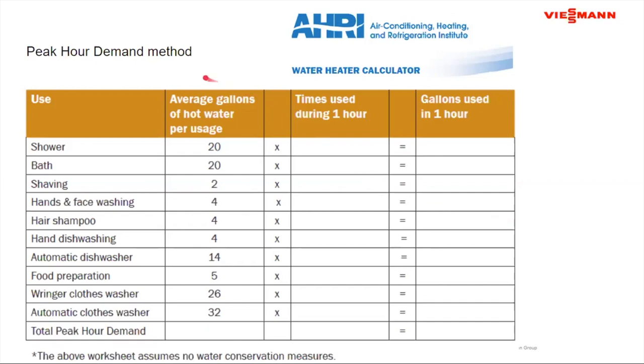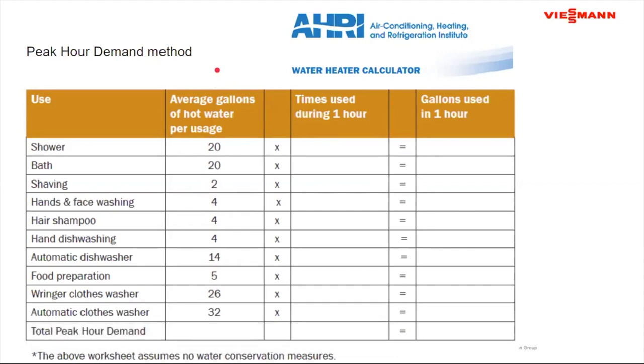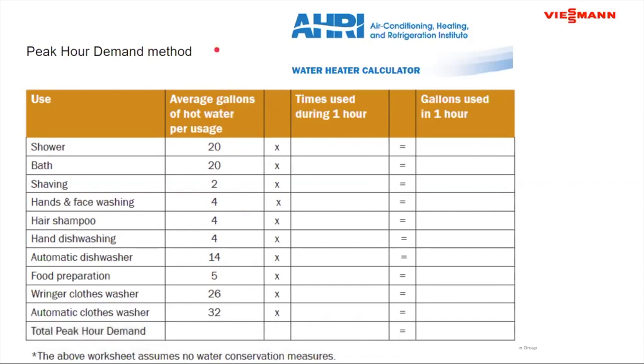So this is a peak hour demand method. Rather than working off of a rule of thumb based on bedrooms or people or bathrooms, it's all about the amount of hot water that's being used per usage of each one of these. So based on the AHRI numbers, remember down here at the bottom, there are no water conservation methods. They say that your average shower uses about 20 gallons of hot water, okay? Your average shaving uses about 2 gallons of hot water. If you're doing hand dishwashing, for instance, it takes 4 gallons. So we'll take these numbers and multiply them by the number of times used during that hour.